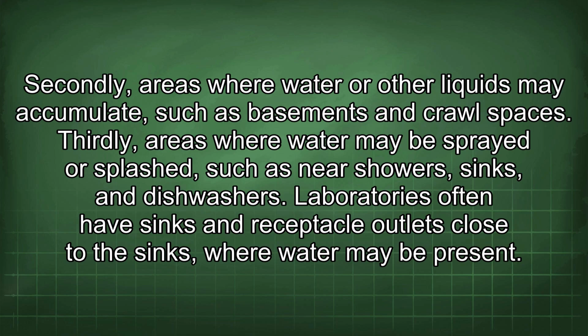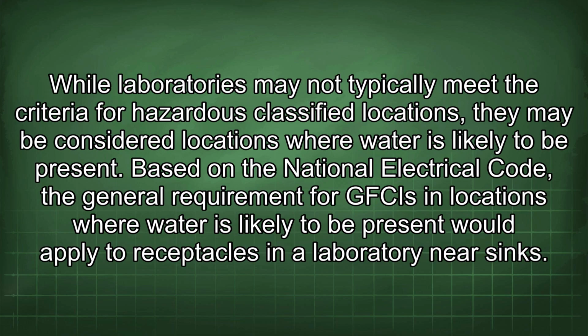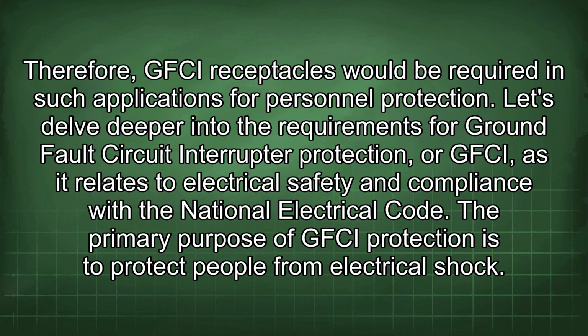Laboratories often have sinks and receptacle outlets close to the sinks, where water may be present. While laboratories may not typically meet the criteria for hazardous classified locations, they may be considered locations where water is likely to be present. Based on the National Electrical Code, the general requirement for GFCIs in locations where water is likely to be present would apply to receptacles in a laboratory near sinks. Therefore, GFCI receptacles would be required in such applications for personnel protection.